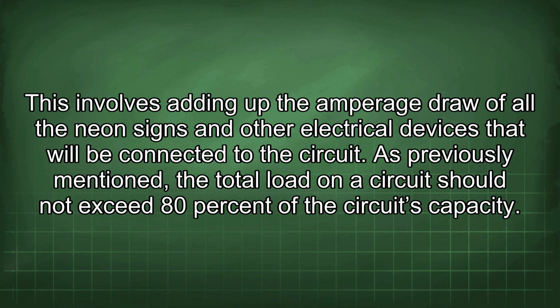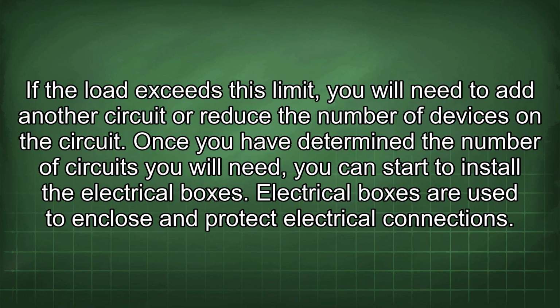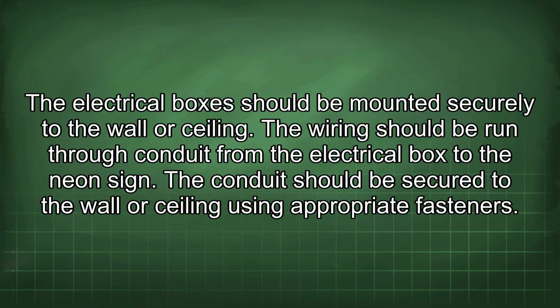This involves adding up the amperage draw of all the neon signs and other electrical devices that will be connected to the circuit. As previously mentioned, the total load on a circuit should not exceed 80% of the circuit's capacity. If the load exceeds this limit, you will need to add another circuit or reduce the number of devices in the circuit. Once you have determined the number of circuits you will need, you can start to install the electrical boxes. Electrical boxes are used to enclose and protect electrical connections. The electrical boxes should be mounted securely to the wall or ceiling.